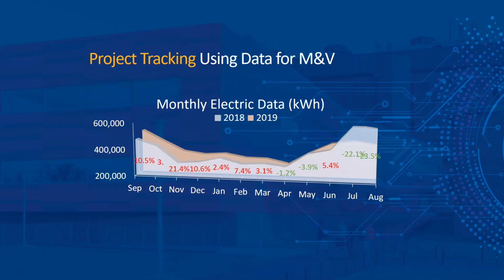The other thing that we use this for, we have a lot of energy projects going on, so we use this to ensure that the energy projects are saving as much as they say they're supposed to. In this case, the blue chart in the front was 2018, and we put a project through in 2019. In the back, you could see that the energy is a little bit higher. So we questioned this, and the problem was the system we put in was not programmed correctly. Once we fixed that, you could see in late June, July, and August the energy really started to come down.